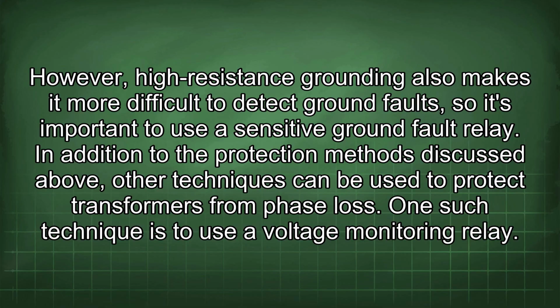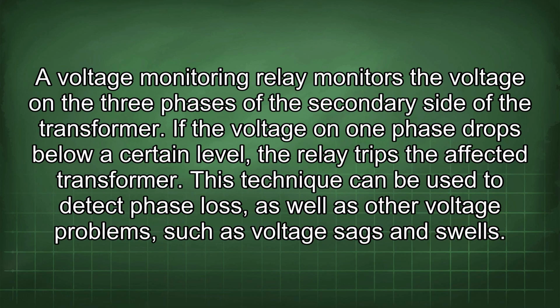In addition to the protection methods discussed above, other techniques can be used to protect transformers from phase loss. One such technique is to use a voltage monitoring relay. A voltage monitoring relay monitors the voltage on the three phases of the secondary side of the transformer. If the voltage on one phase drops below a certain level, the relay trips the affected transformer.